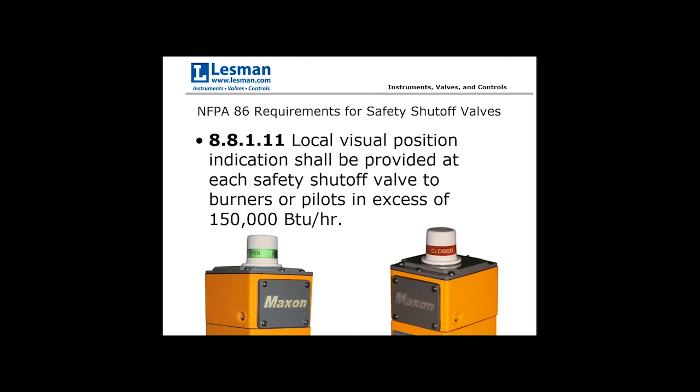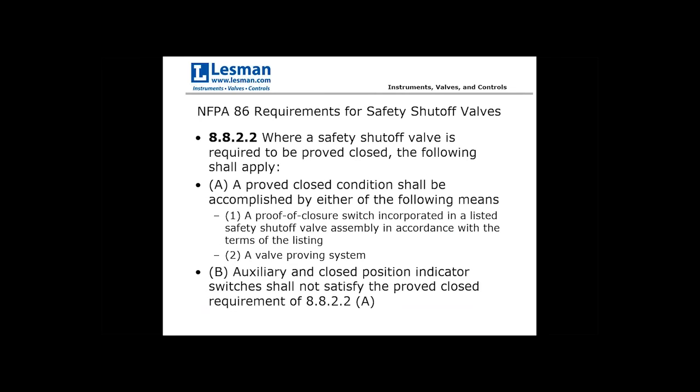Requirements for safety shutoff valves include local visual position indication — specifically for any burners or pilots exceeding 150,000 BTUs per hour. Simple solenoid valves like ASCO without visual indication are acceptable for smaller pilots at 20,000–40,000 BTUs per hour, but above 150,000 the code requires visual indication. There is also a requirement where a safety shutoff valve is required to be proved closed: the proved closed condition shall be accomplished by a proof of closure switch incorporated in a listed safety shutoff valve assembly, or by a valve proving system.